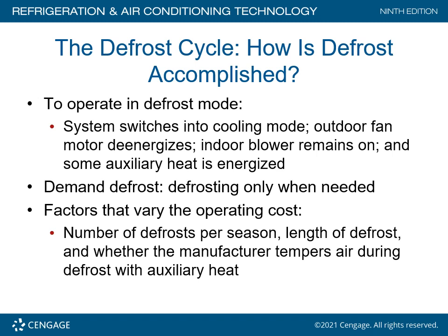Demand defrost, defrosting only when needed. Typically on our modern systems, we only defrost the coil when it absolutely needs it. This is done electronically through the use of sensors. Factors that vary the operating costs: the number of defrosts per season, the length of the defrost, and whether the manufacturer tempers the air during defrost with auxiliary heat.